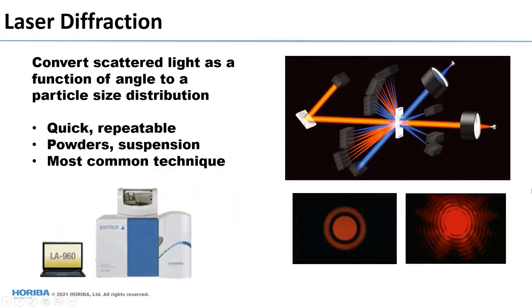Laser diffraction looks at scattered light as a function of angle to convert into a particle size distribution. You have a laser, a sample, and detectors at a number of different angles. As you move from the center out, you'll see scattering as rings or peaks, and interpreting these rings gives us the size distribution. Advantages: it's very fast — you can get a measurement in just a minute or so. It's very repeatable, and you can use it for dry powders, liquid suspensions, and emulsions. It also covers a very wide range of sizes.